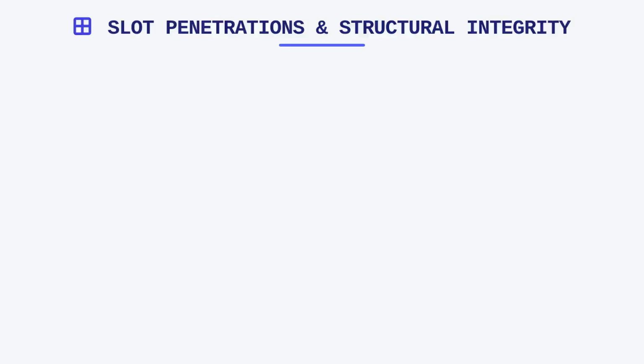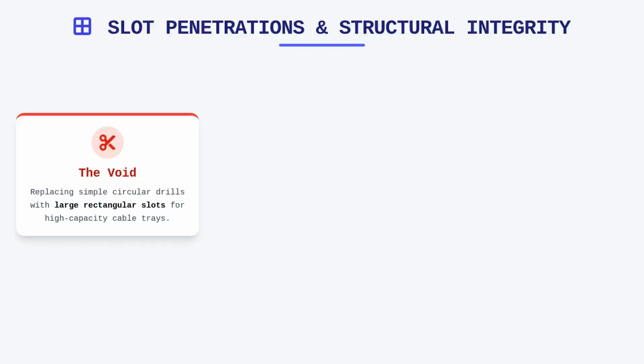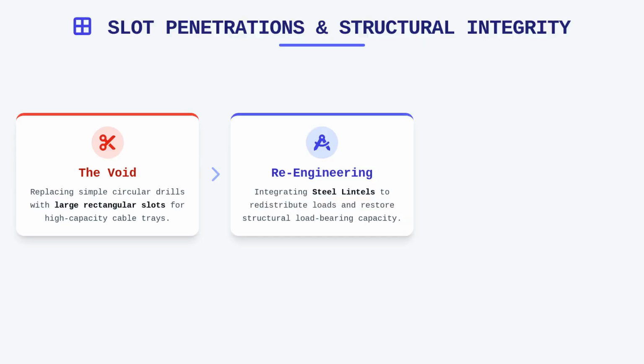Moving beyond simple circular penetrations, we occasionally face the need to route high-capacity pathways like cable trays through fire-rated walls. This requirement necessitates the design and installation of slot penetrations, which are considerably more complex than standard core drills. When we cut a large rectangular opening for a tray, we create a significant void that fundamentally alters the load-bearing characteristics of the wall or slab. To regain the necessary structural capacity, we must integrate reinforcement members, such as steel lintels, to distribute the load around the perimeter of the opening.